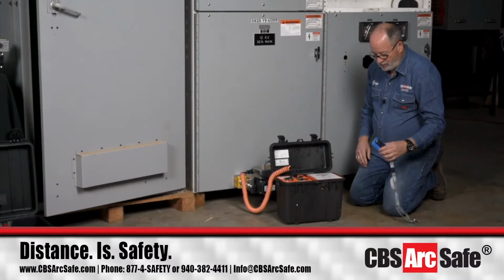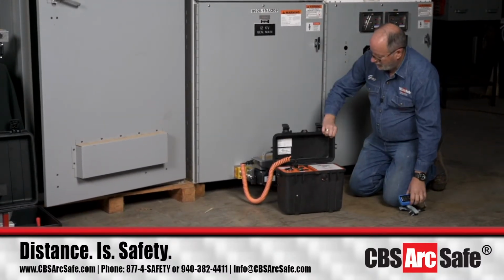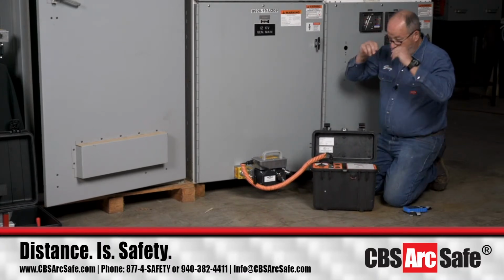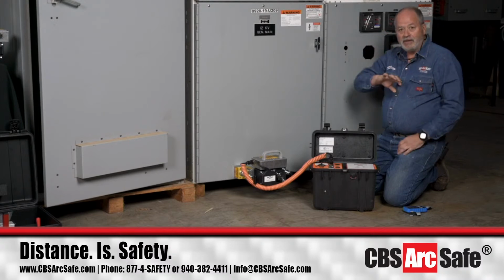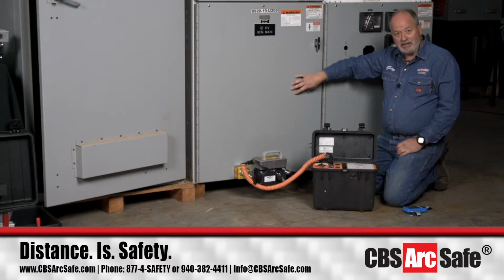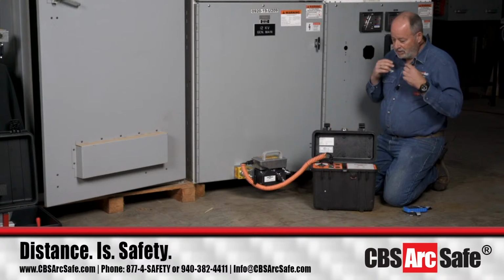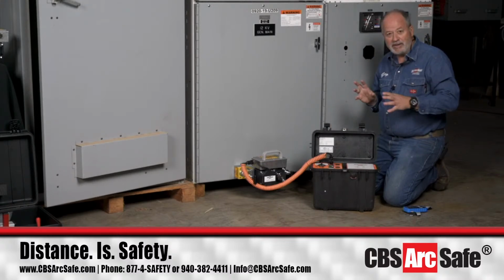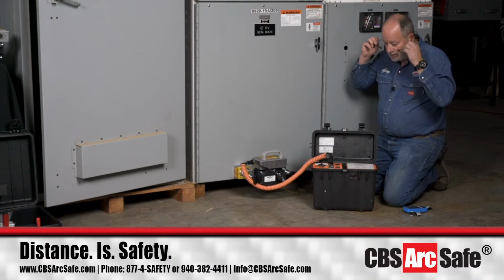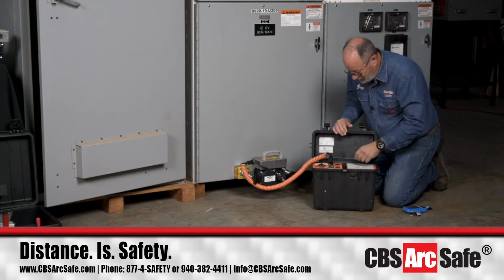We use the RS04. This one's got a handheld remote we can use. I'll take this off at the end, but the first thing that has to happen, and the reason we've already got this mounted on there, is there's an interlock that has to push in about 1.5 inches to be able to engage the racking mechanism and expose the racking mechanism. And when that interlock gets pushed in, if you haven't tripped the breaker yet, it's supposed to trip the breaker. Okay, so that's how this thing is set up and designed. It takes about 25 pounds of force to push that in and mount everything. So they already got it set up for me, and when I take it off, we'll take it off.